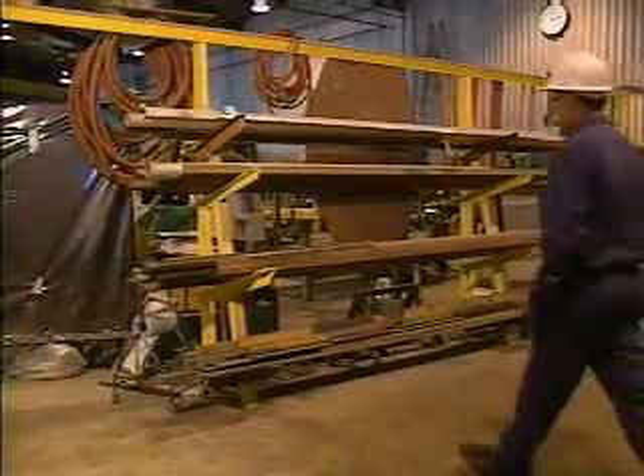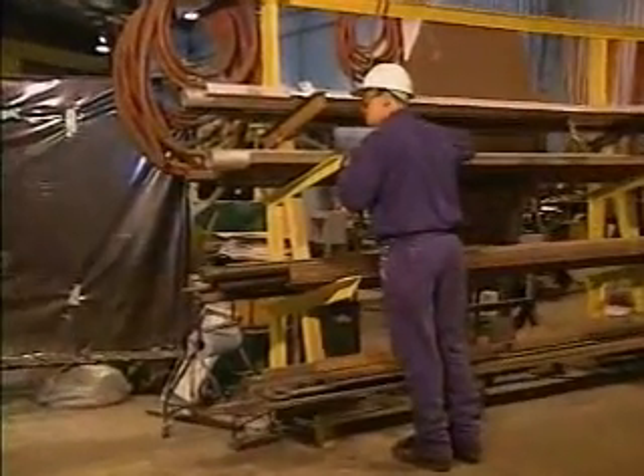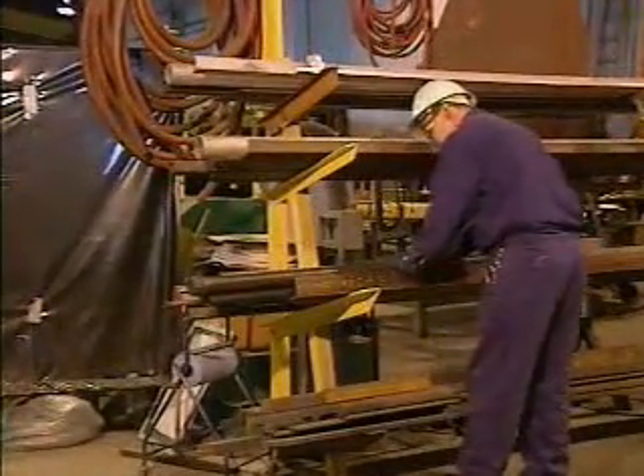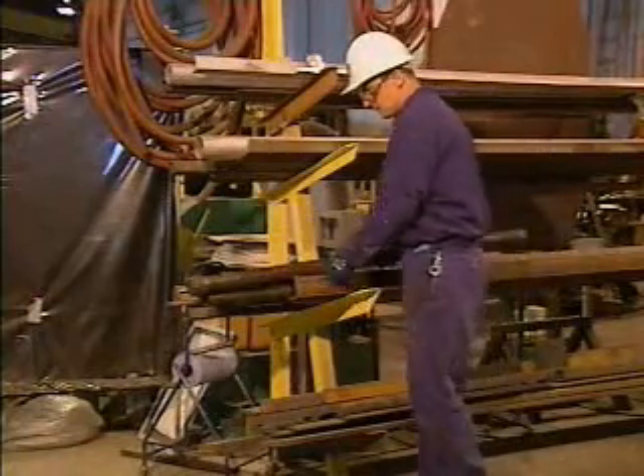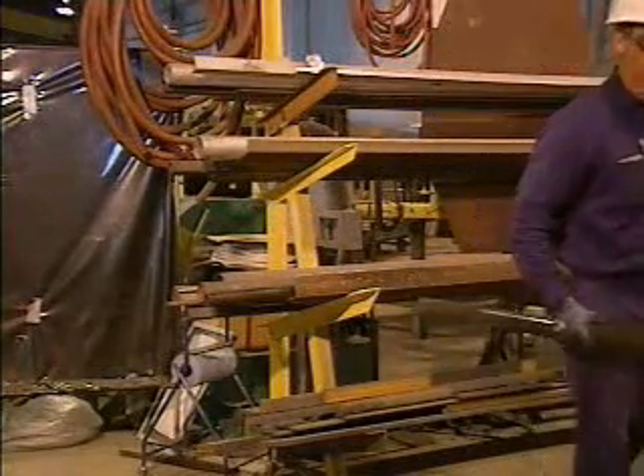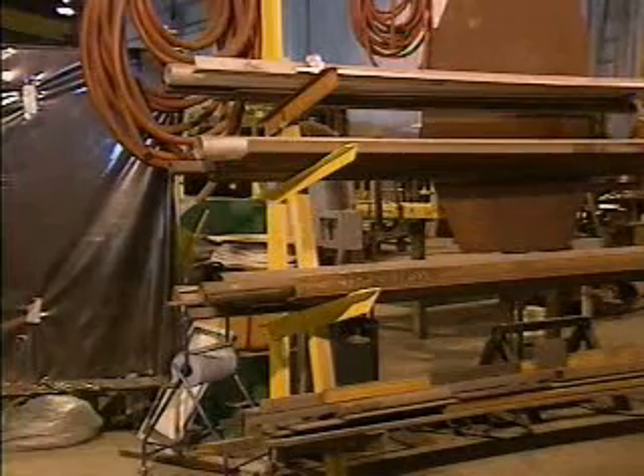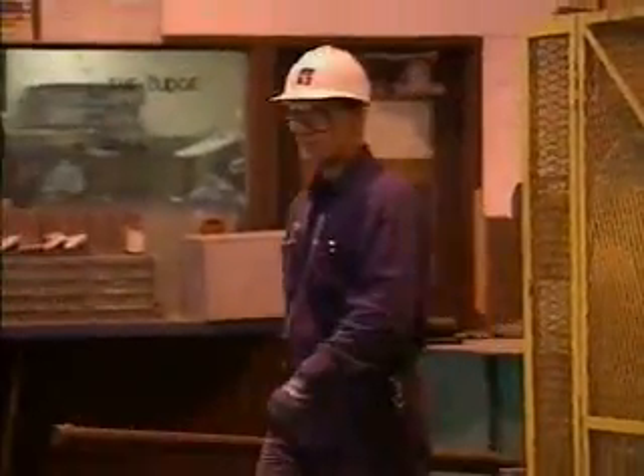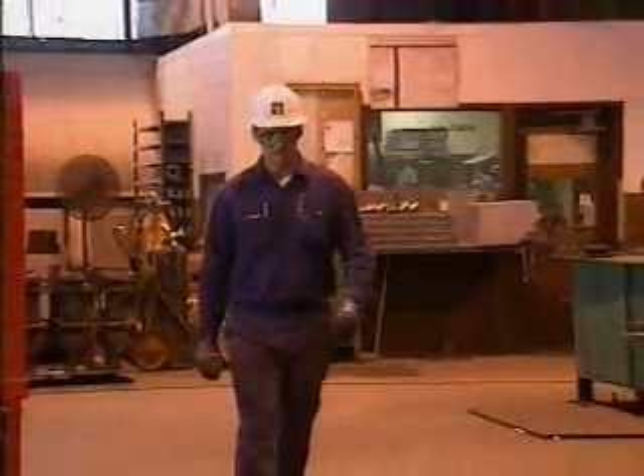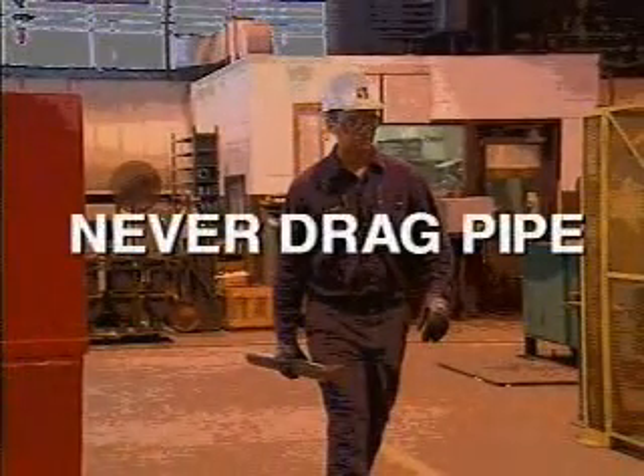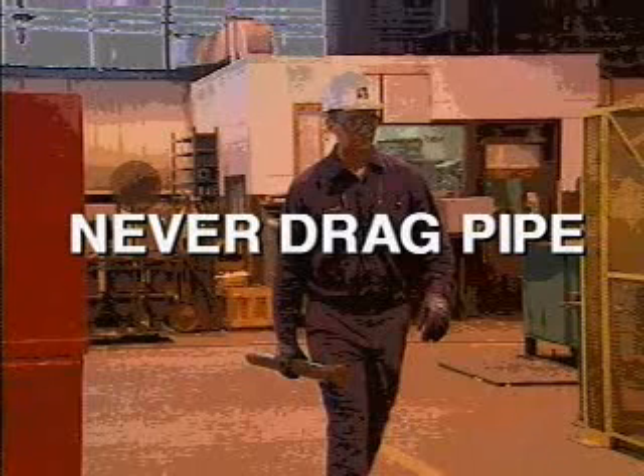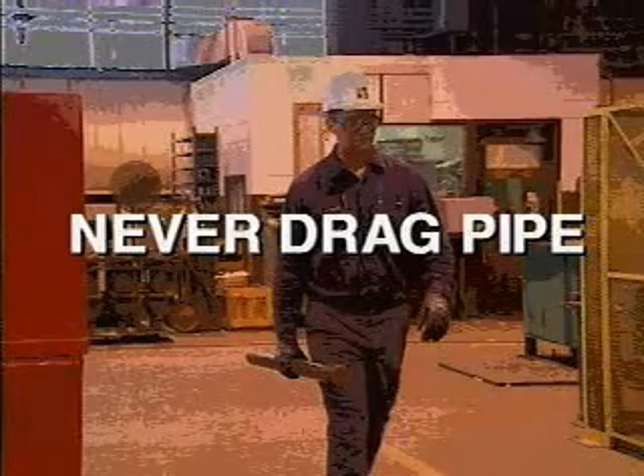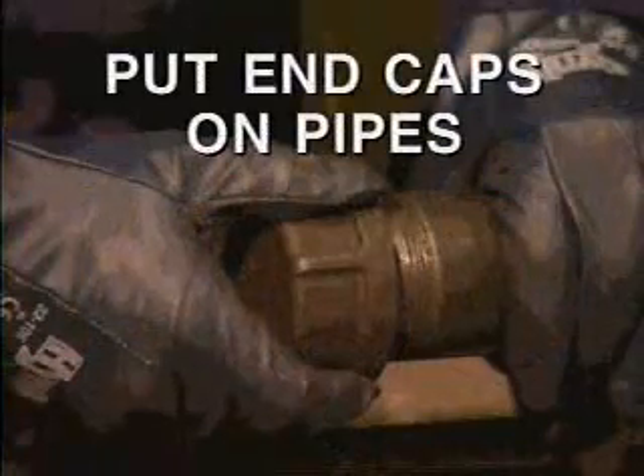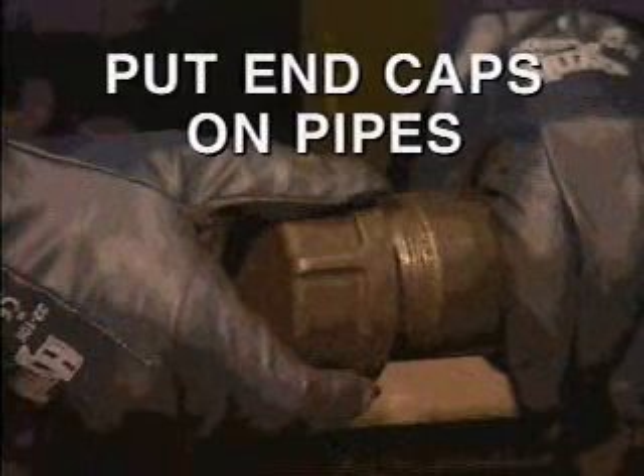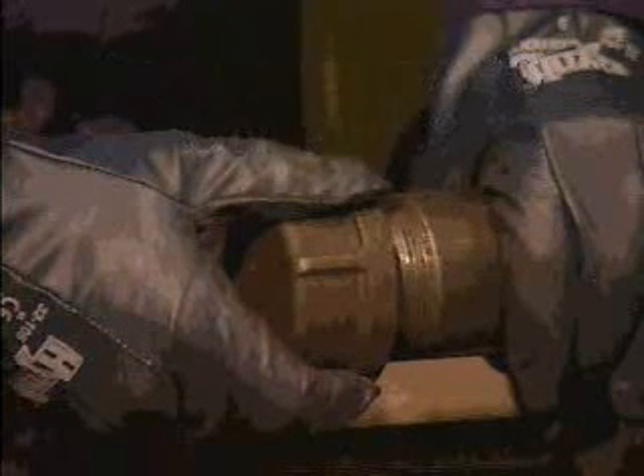Much of the wear and damage looked for during an inspection, such as dents, can be reduced if pipes are handled safely and properly. Handling pipes safely and properly can also help prevent injuries to personnel working with or around pipes. Safe and proper handling of pipes includes the following basic guidelines. Never drag pipes. Dragging a pipe can scratch or dent the outside surface, damage the ends, or contaminate sterilized pipe. Put end caps on pipes during handling and transport to guard against damage and contamination.